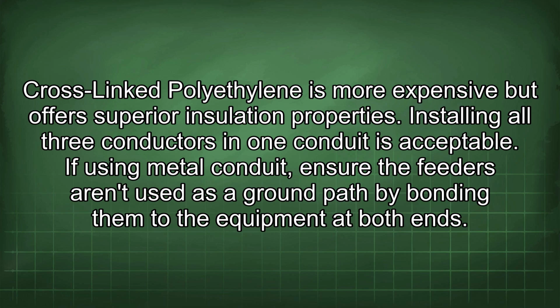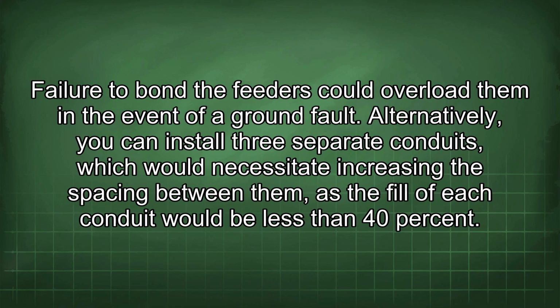If using metal conduit, ensure the feeders aren't used as a ground path by bonding them to the equipment at both ends. Failure to bond the feeders could overload them in the event of a ground fault. Alternatively, you can install 3 separate conduits, which would necessitate increasing the spacing between them, as the fill of each conduit would be less than 40%.